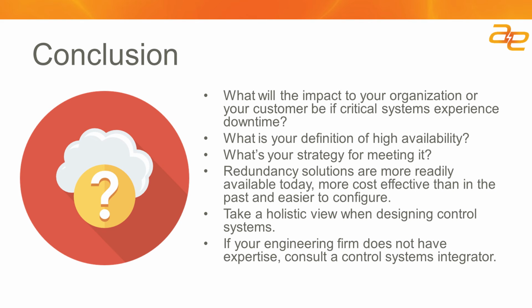You also want to make sure that when designing your systems, you take a holistic view. Don't put on blinders and think you're solving the problem by installing a redundant PLC while leaving instruments, networks, or even your SCADA system vulnerable. Even if you design a redundant PLC but have a network with a single point of failure, your investment in that redundant PLC may be significantly diluted.